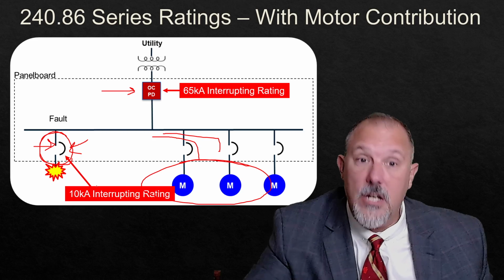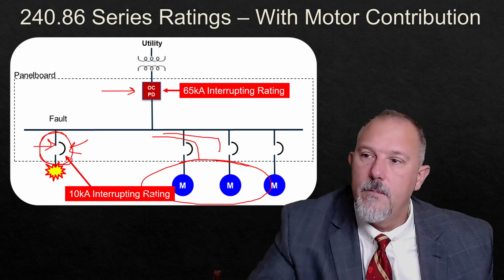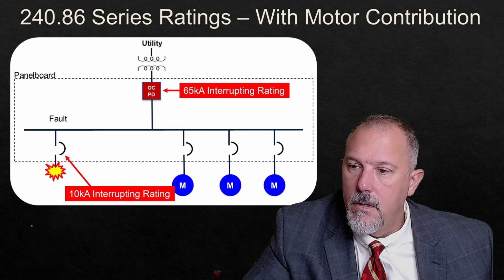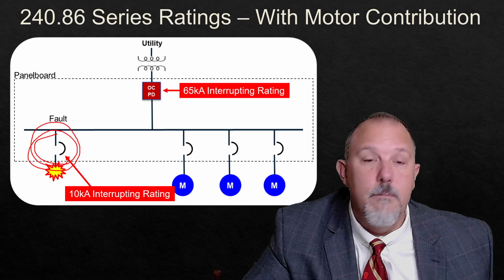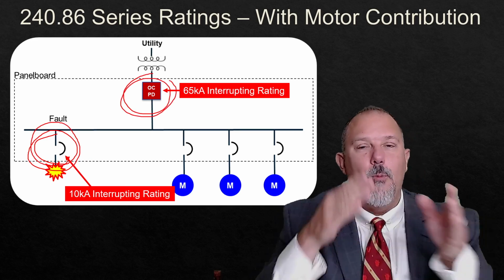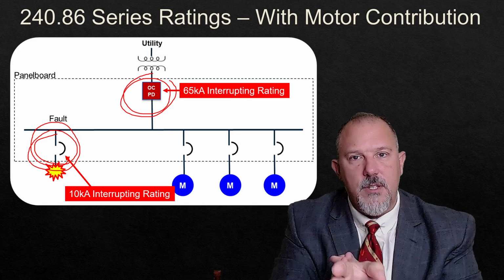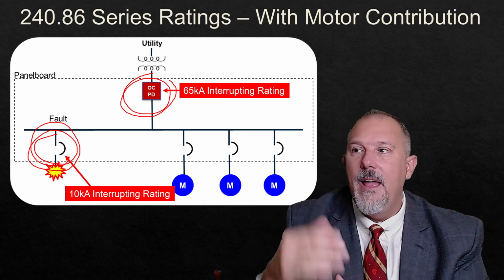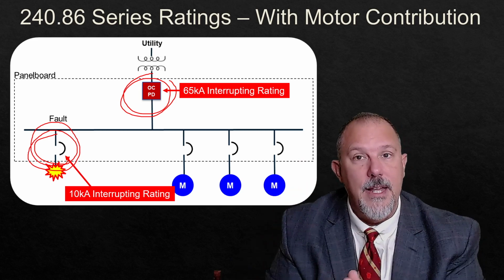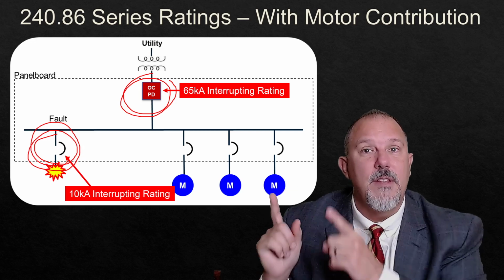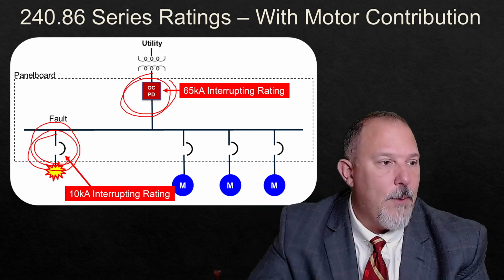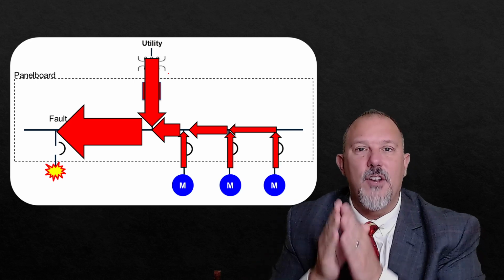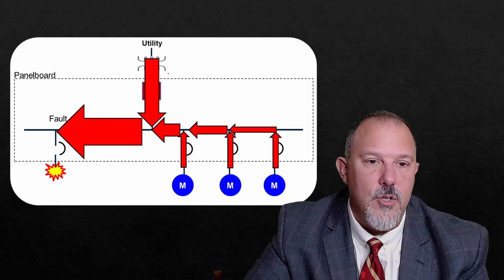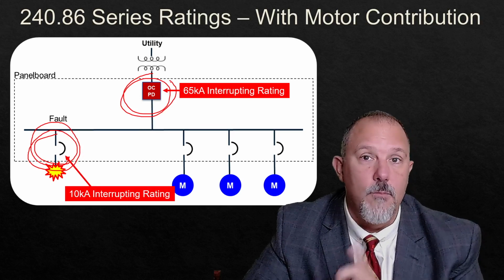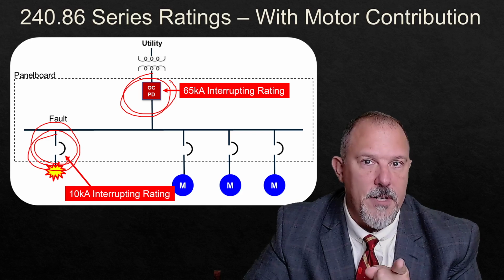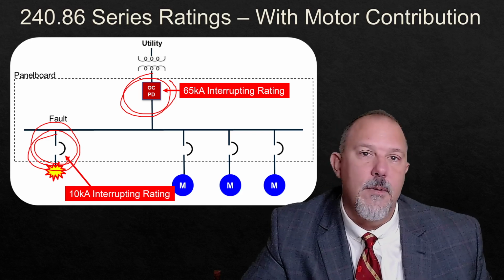Make sense? Because why? The downstream circuit breaker, this guy right here, will see more current than this guy. When they test series rated pairs, they put two circuit breakers in series, they pass the same amount of current through both of them, and they will both open to stop the flow of that current. In this case, there's more current flowing through the downstream breaker than there is through the upstream breaker. Why do I know that? Because of the path of current that flows in this circuit. So I want to make sure that my downstream breaker does not see more than 1% of its interrupting rating, a full load amps of any motors that are connected in between these two.